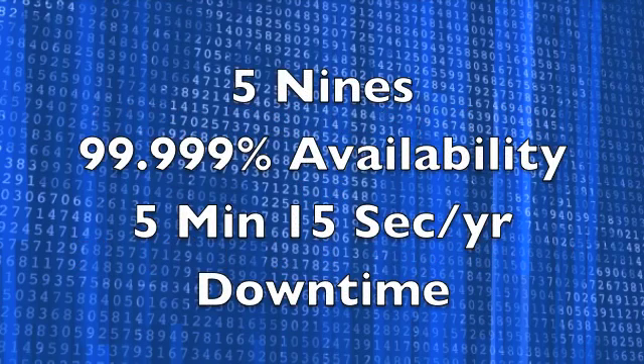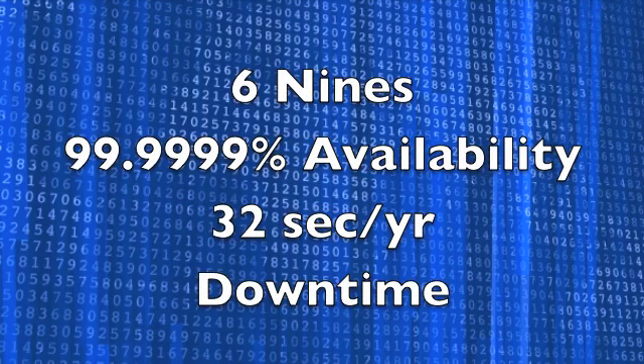Here are some handy numbers to give you perspective on the whole nines issue. Five nines, or 99.999% availability, means five minutes, 15 seconds or less of downtime in a year. Or if you're really ambitious, shoot for six nines, or 99.9999% availability. That allows just 32 seconds or less of downtime per year.